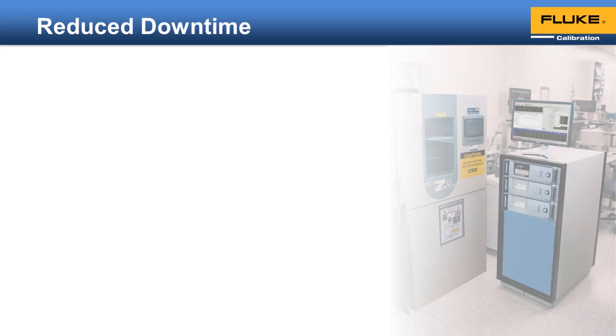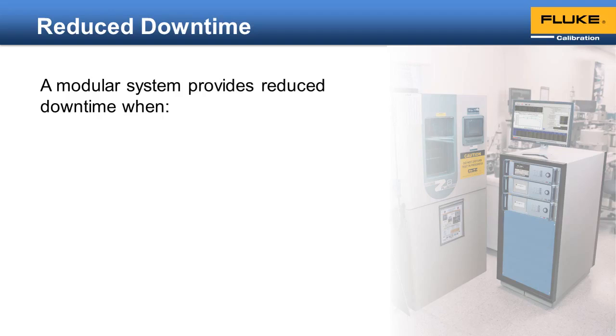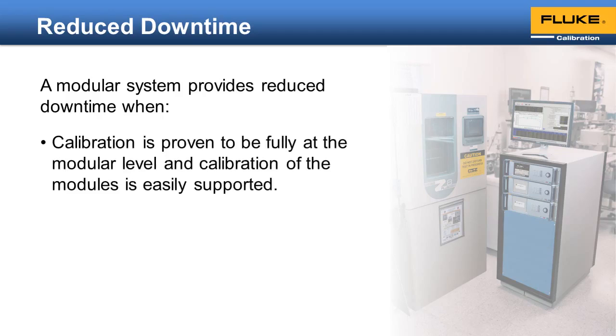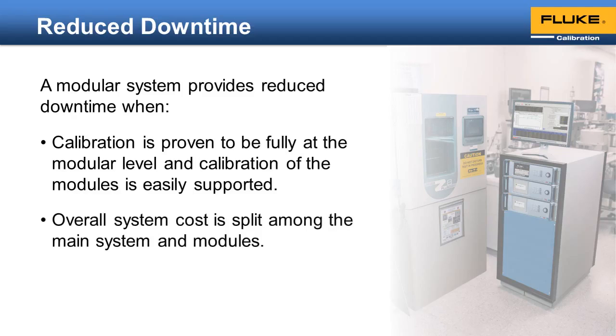A calibration standard inherently has some downtime, because at some point it needs to be recalibrated itself. A true modular system reduces or eliminates this issue by having all calibrated items encapsulated into one module that can be easily removed. Now only the module needs to be sent in for recalibration. While out, you can still use the other ranges or install backup modules, allowing for 100% uptime. This is only reasonable if the system cost is split among the main system and the modules. It doesn't provide any benefit if a spare module costs the same as a spare controller.